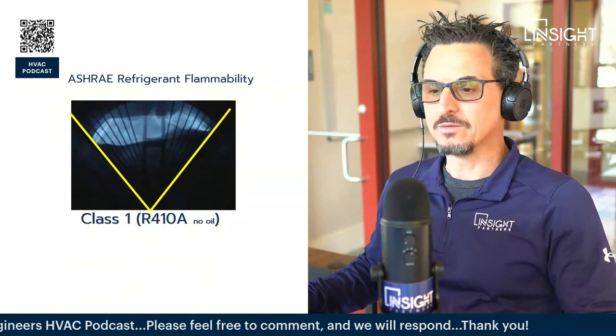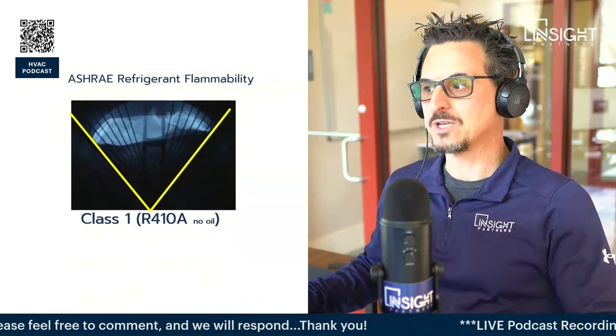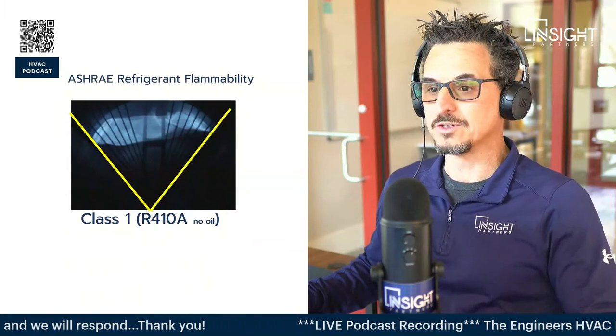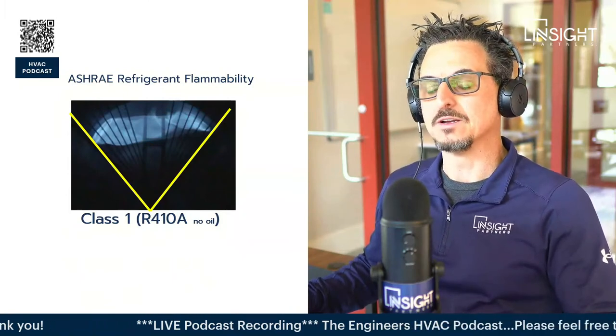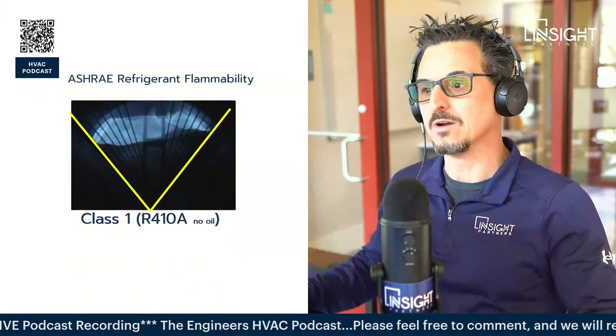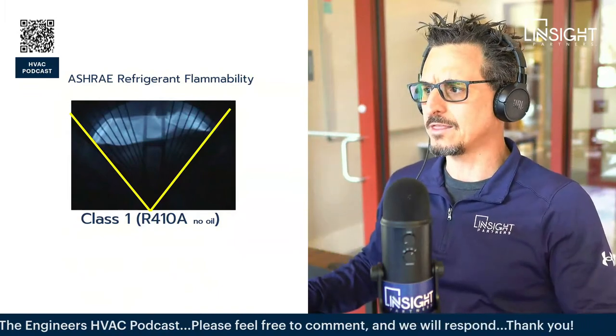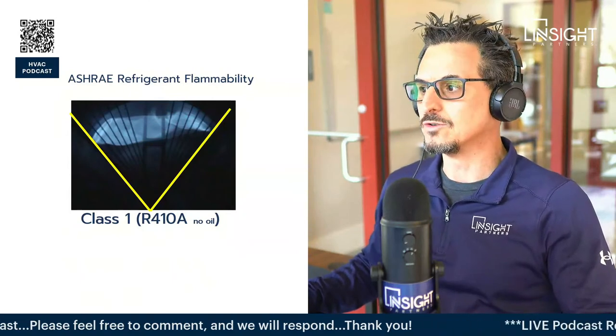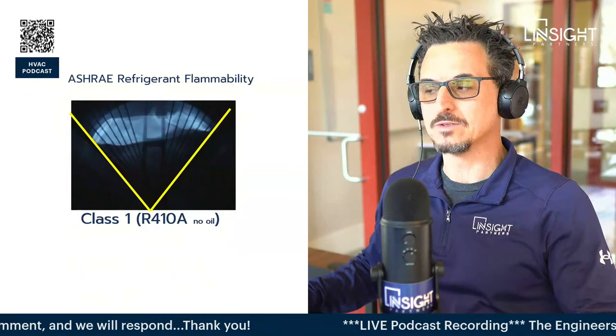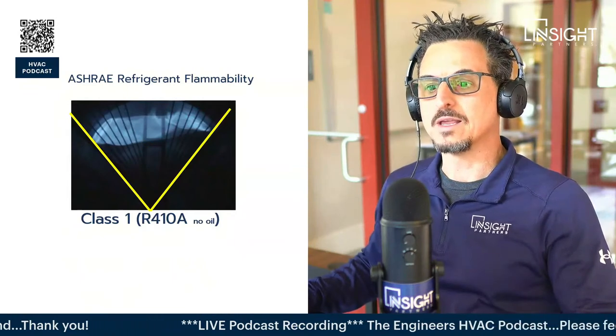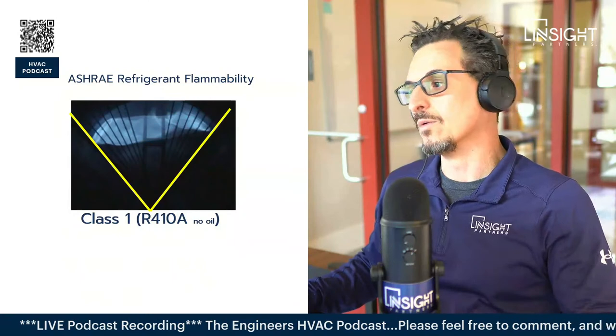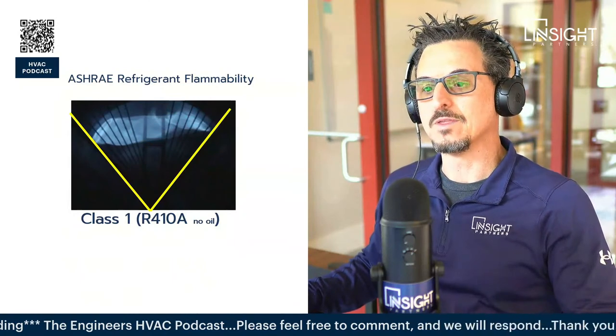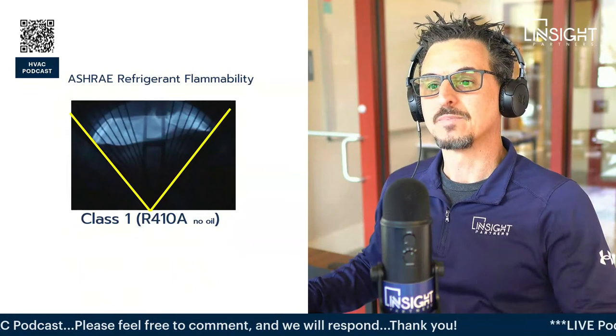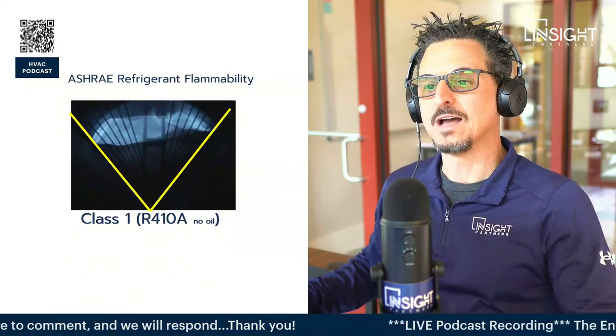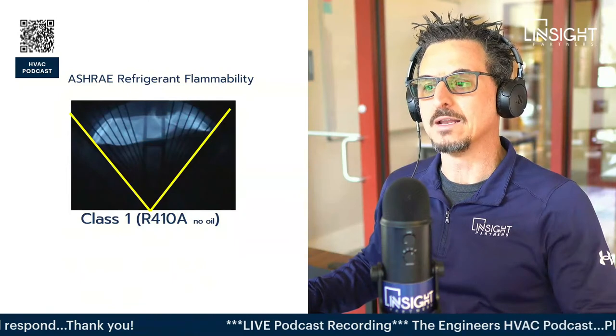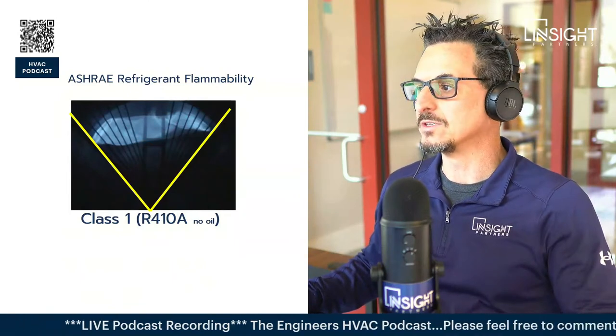This says it all for me, this was really helpful. This is a snapshot of a test chamber where they actually ignite the refrigerant and look at the propagation of the flame, meaning how much it basically expands and grows as it burns. I think they use like a 3000 degree torch to light these, because some of these A2Ls are really hard to ignite. This one right here is a class one, or what we called an A1 before, 410A with no oil. This is what it looks like in the chamber. You see these black lines - we've highlighted these in yellow to show you the outline of the propagation of the flame for 410A.